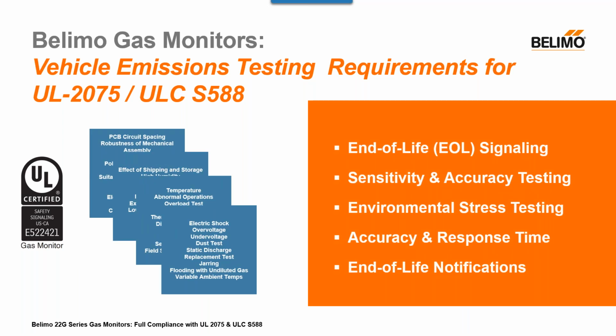Some of the key elements of the UL 2075 certification include end-of-life signaling. The standard requires gas monitors to have end-of-life indicators that notify users when the sensor is no longer functional. This feature prevents users from relying on expired or ineffective devices, thus ensuring continuous protection.